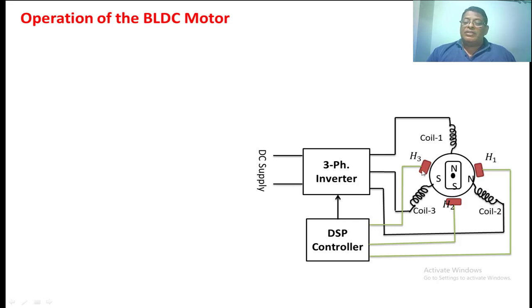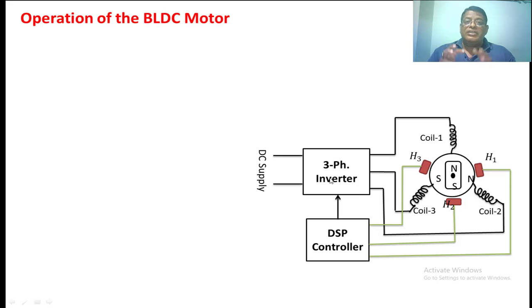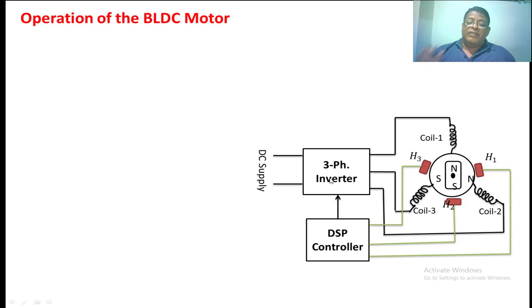The main function of these Hall effect sensors is to give information about the position of the rotor. Based upon that, the DSP controller generates a pulse through the 3-phase inverter. This inverter gives a pulse to the stator winding, where exactly the force will be created from the stator winding.